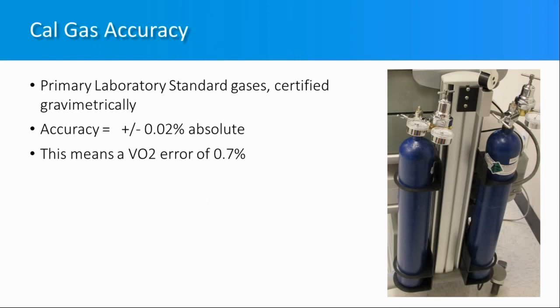Regarding calibration gas, the system is only as good as your ability to trace back to scientific standards. If you have a calibration gas with more than about 0.02% absolute error, you are starting to fall outside of acceptable limits, especially when working with athletes or in research contexts.